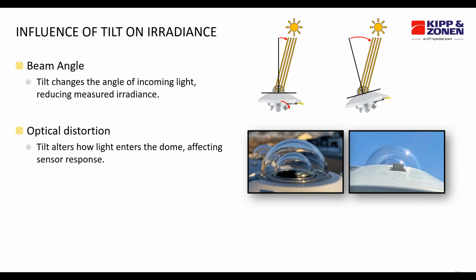All Class A pyranometers have high-end optical glass or similar material domes covering the sensors. And despite the high clarity and uniformity these domes are required to have, they can still contain slight imperfections that alter how light enters the dome and ultimately how many photons reach the detector to create a signal. And the pyranometer on the right here has been deployed for a while. If you look at the small reflections and things on the glass, the glass can get optical distortions over time being deployed, such as from sand pitting or scratching during maintenance, or even soiling on the dome, things like that.